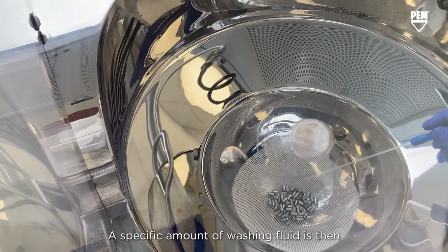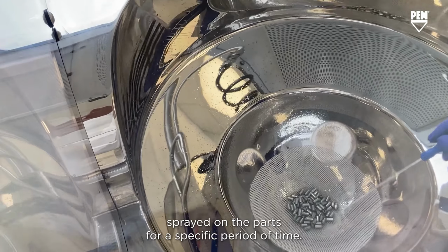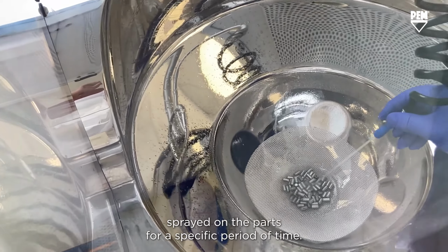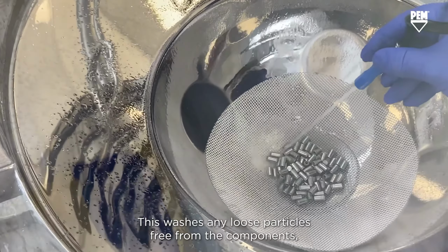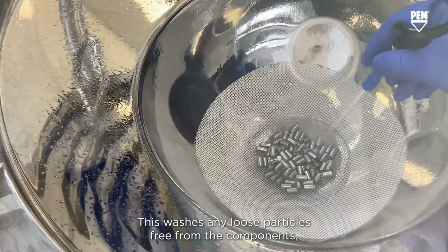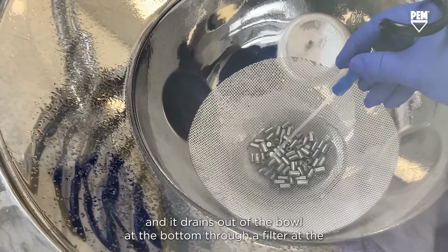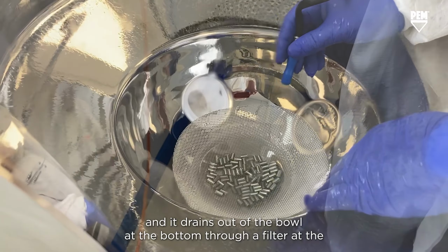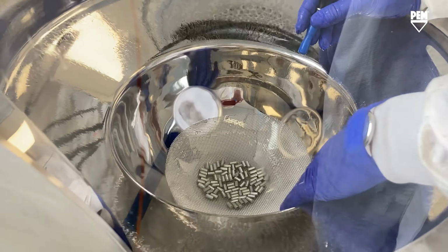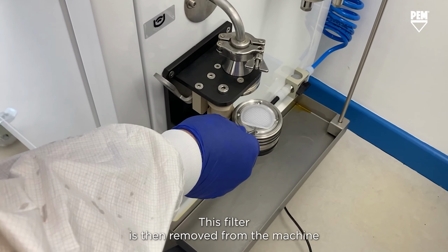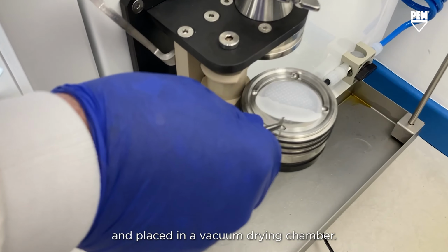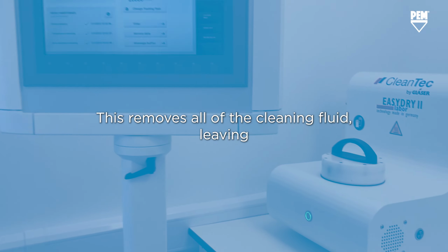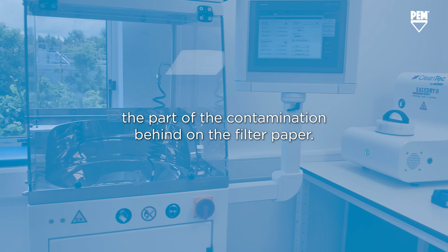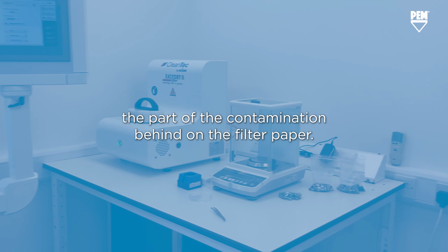A specific amount of washing fluid is then sprayed on the parts for a specific period of time. This washes any loose particles free from the components, and it drains out of the bowl at the bottom through a filter at the side of the machine. This filter is then removed from the machine and placed in a vacuum drying chamber. This removes all of the cleaning fluid, leaving the particle contamination behind on the filter paper.